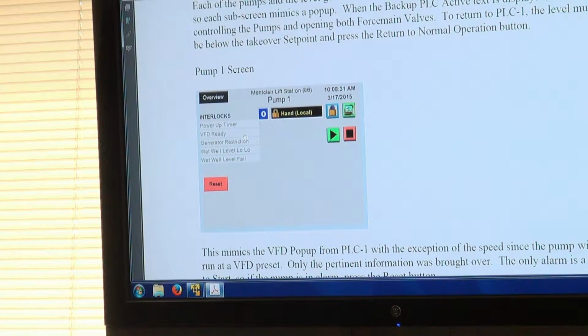Now, if you are on generator, the PLC is running 2, and you try to start the 3rd, the moment it gets running, the other 2 pumps are going to stop, and then one's going to restart after 3 minutes, because both of these suddenly see 3 pumps running, and they're both going to stop. We're pretty sure it can run because they're VFDs. So keep in mind, if you want to try to run 3 pumps on the generator, you're going to have to run all 3 in hand, not just the 3rd pump, because you're going to drop the other 2. It's not recommended, but when Joe was out there, he was like, give me more. We were running 2 pumps at 100%, and he said there was probably more than enough power available for a 3rd to start.